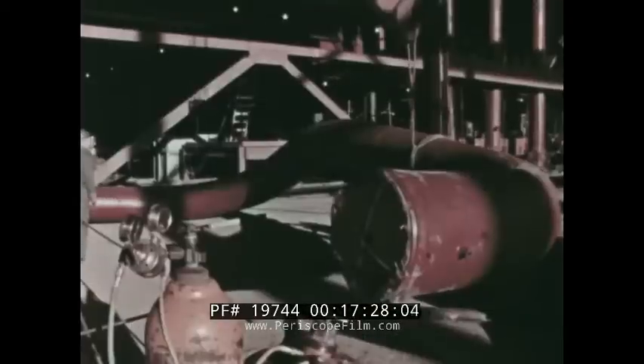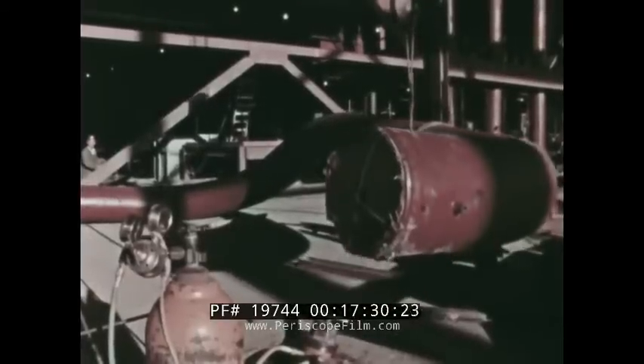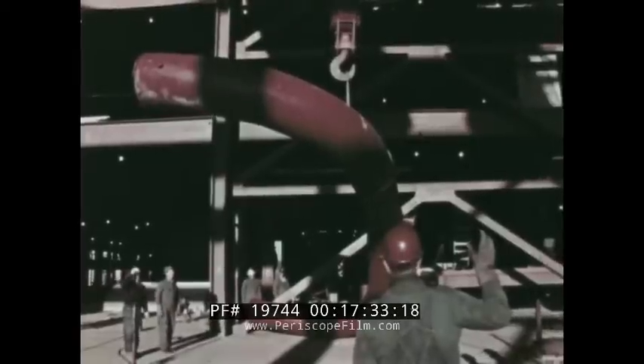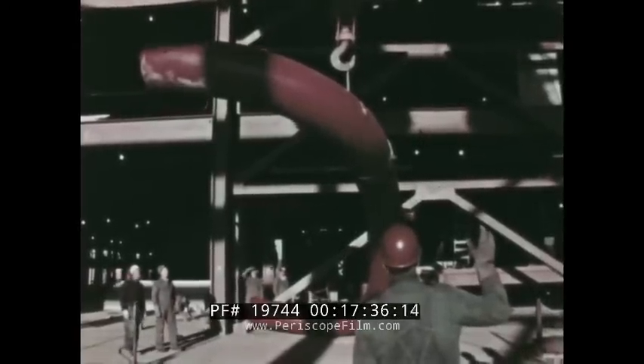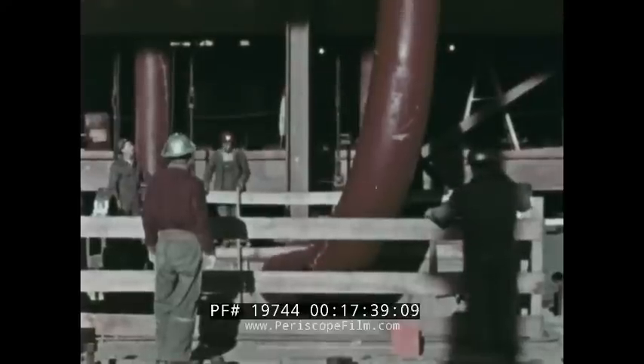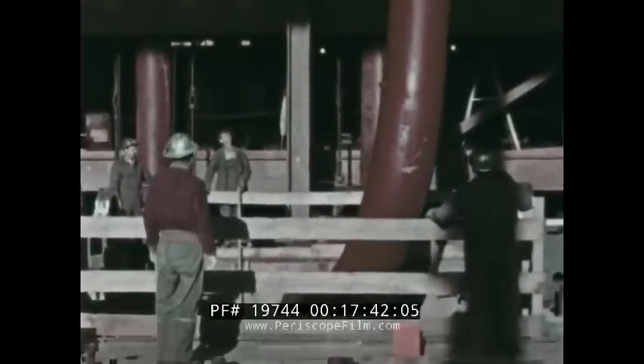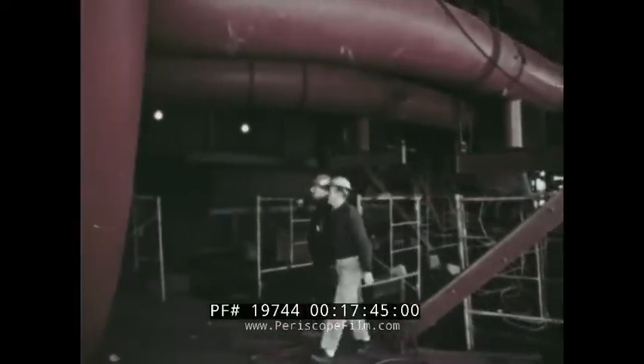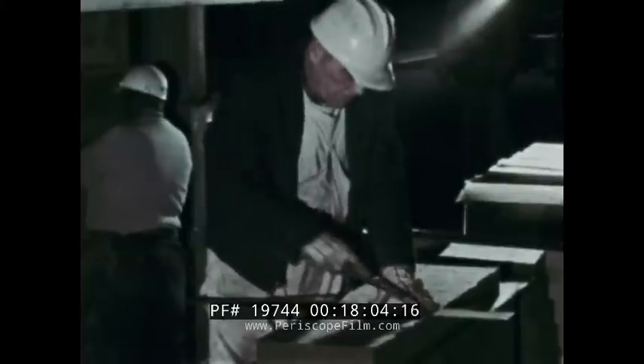The steam leaves the boilers at a temperature of 1,053 degrees Fahrenheit. It is conducted to the turbo generators through pipes made of super-strength, low-alloy steel and manufactured by a process similar to that used for big naval guns. Welding the joints in the alloy pipe required special skills. Welders worked in shifts around the clock while the metal was maintained at a temperature of 500 degrees. Each joint required about 65 hours. Boilers and steam lines must be heavily insulated.